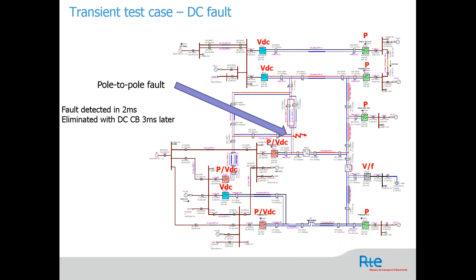So let's start first with the protection activation of each station. Here you have an example to see, when you have a DC fault at this point, the time required for each converter before it trips. So since the DC fault is at the BB1, the first thing we can expect is that the CBB1 should be the first one to trip, and the first one the protection will detect, of course, because this is the closest station. So as we can expect, you can see that this is the fastest one.